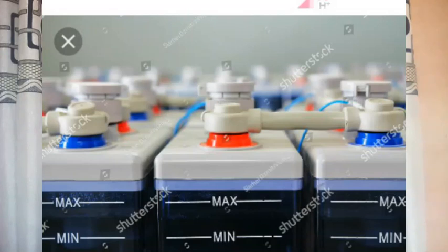That means you've achieved the establishment of a 50-volt battery bank. Connect 25 cells of 2 volt each in series. At the end, the summation will be 50 volts DC. That means you have achieved the 50-volt battery bank's arrangement.